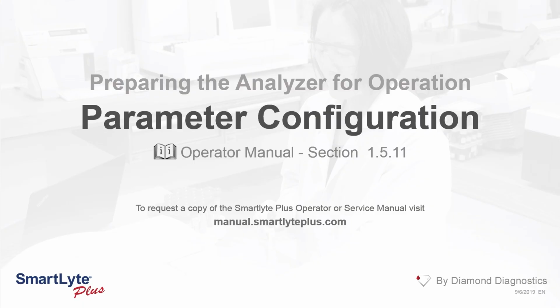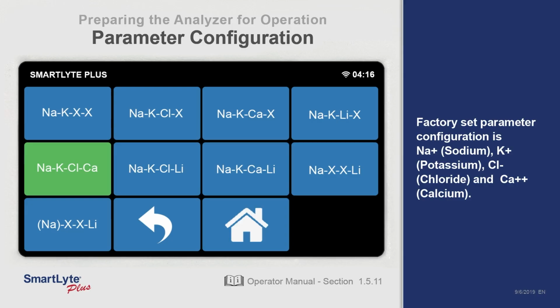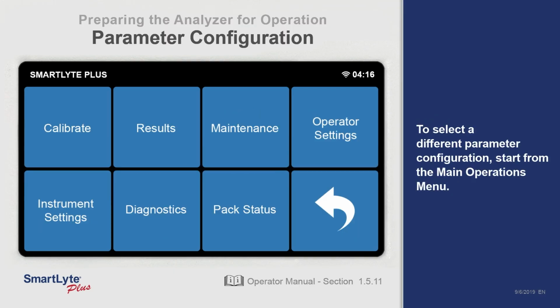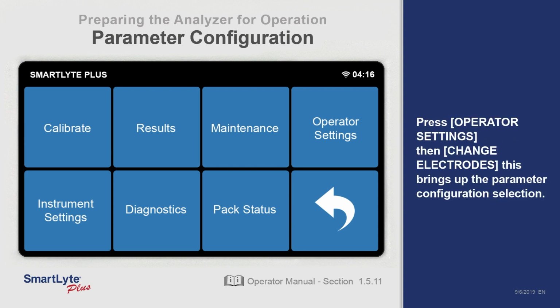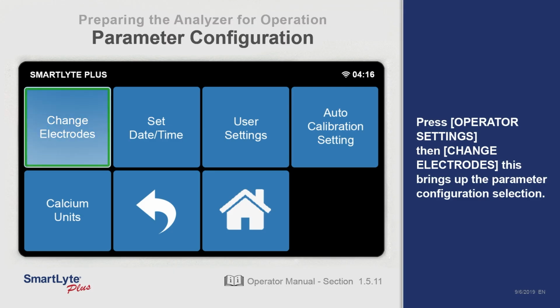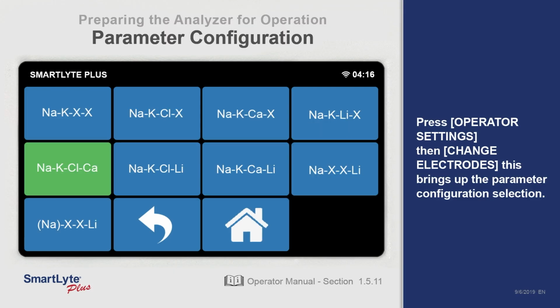Parameter selection on the SmartLyte Plus. The factory set parameter configuration on the SmartLyte Plus is sodium, potassium, chloride, and calcium. To select a different parameter configuration, start from the main Operations menu. Press Operator Settings, then Change Electrodes. This will bring up the parameter configuration section.